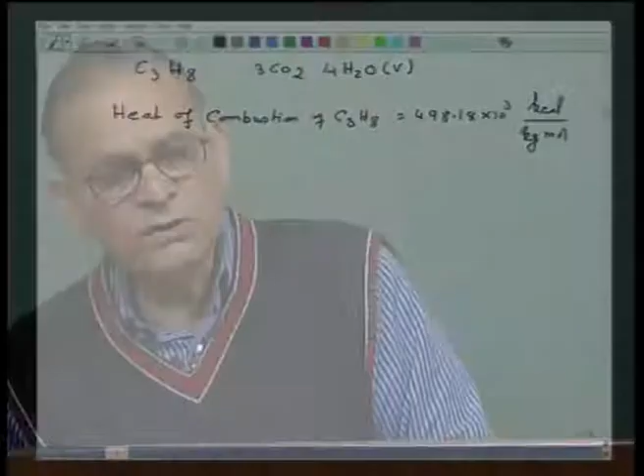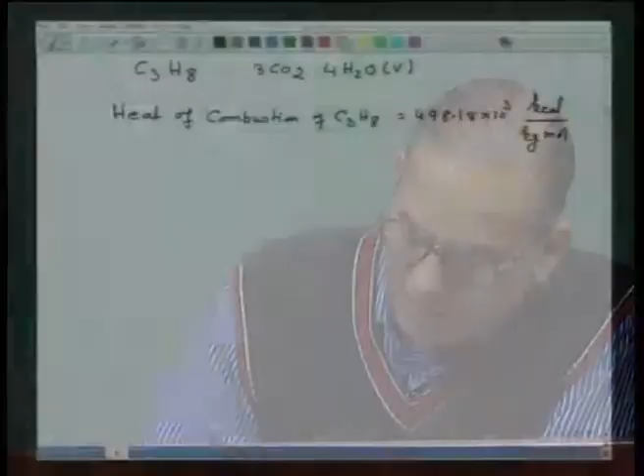Now, note that these values belong to when H2O is in the vapor state. So, we can call it the net calorific value. Therefore, the net calorific value of natural gas of the composition which I have given earlier, taking the lower percentage of CH4, will be equal to 0.81 into 194.91 into 10 to the power 3 plus 0.03 into 350.56 into 10 to the power 3 plus 0.005 into 498.18 into 10 to the power 3. So, this is the net calorific value of 1 kg mole of natural gas. Adding them together, we will be getting 170.91 into 10 to the power 3 kilocalorie per kg mole of natural gas.